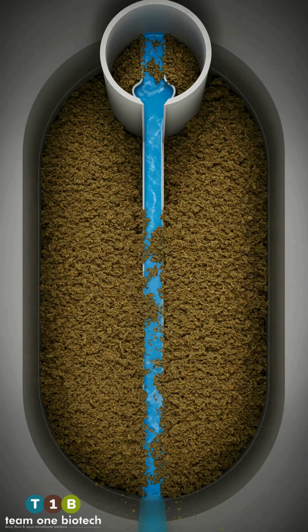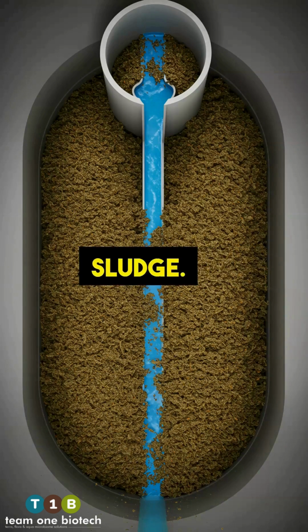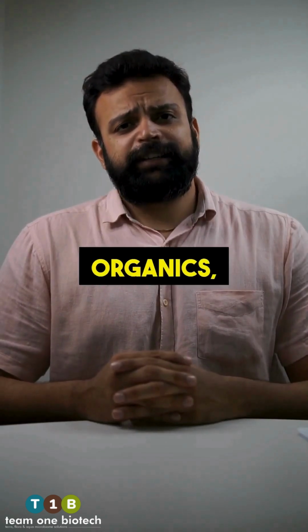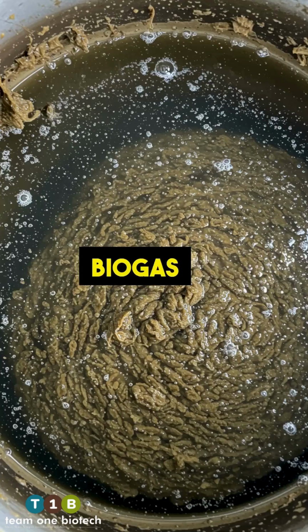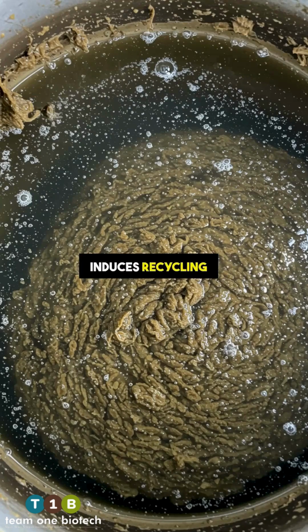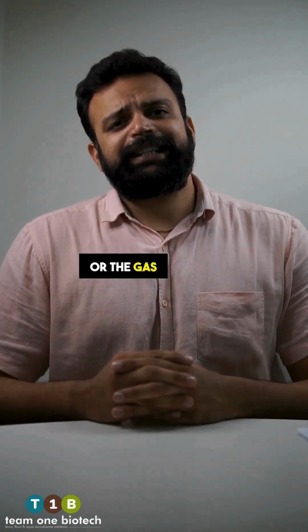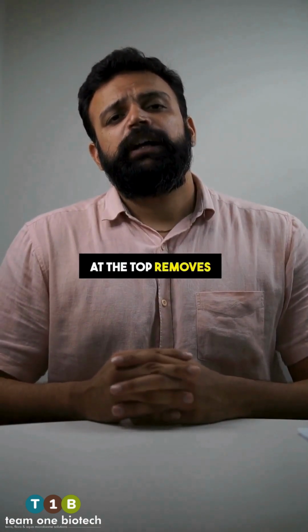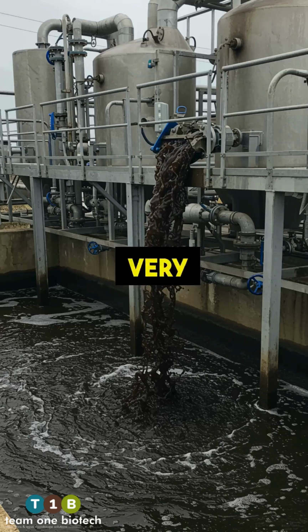The UASB. In this process, effluent flows upward through a blanket of granular sludge. The granules trap organics, the microbes degrade it. Biogas forms in situ, induces recycling and formation of sludge. The GLSS or the gas liquid solid separator at the top removes biogas and recycles sludge. This type of process is very efficient in high to medium strength COD effluent.